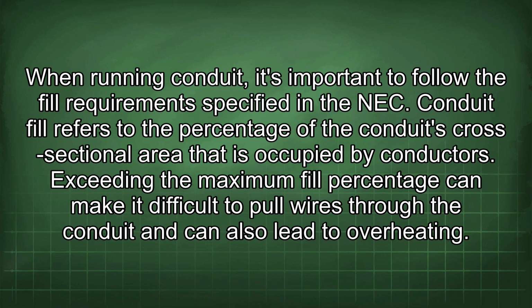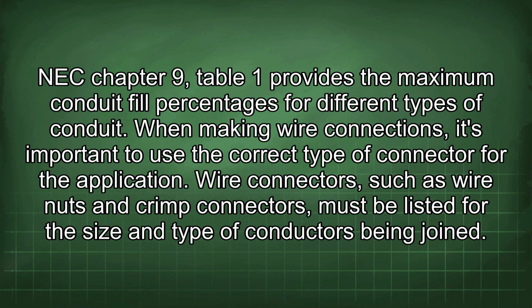Conduit fill refers to the percentage of the conduit's cross-sectional area that is occupied by conductors. Exceeding the maximum fill percentage can make it difficult to pull wires through the conduit and can also lead to overheating. NEC Chapter 9, Table 1 provides the maximum conduit fill percentages for different types of conduit.